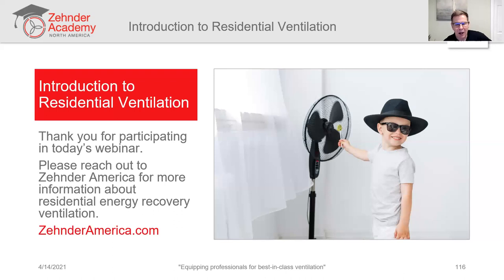Now you ask, can you press up against that limit? And the answer is you could operate all the time up to 218 CFM. The problem with that is the unit is engineered around a sweet spot, or a range, I should say. And that 100 to 120 CFM range is where you're going to get optimal fan performance. In other words, your watts per CFM, or CFM per watt, whichever way you want to look at it. That's the efficiency of your fan operation, and not only that, but the efficiency of the energy recovery out of the heat exchanger.